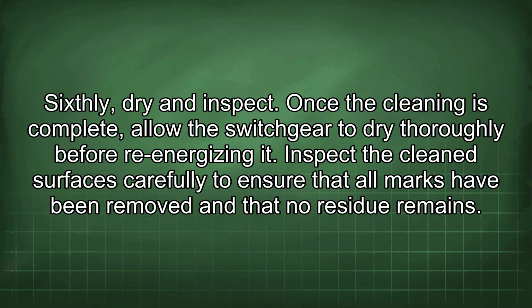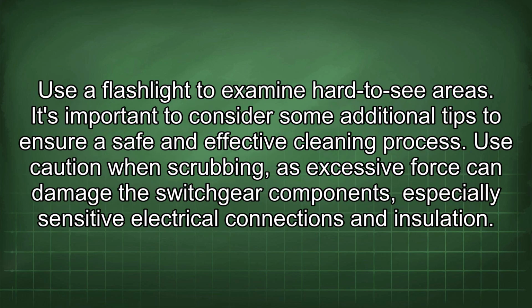Sixthly, dry and inspect. Once the cleaning is complete, allow the switchgear to dry thoroughly before re-energizing it. Inspect the cleaned surfaces carefully to ensure that all marks have been removed and that no residue remains. Use a flashlight to examine hard-to-see areas.